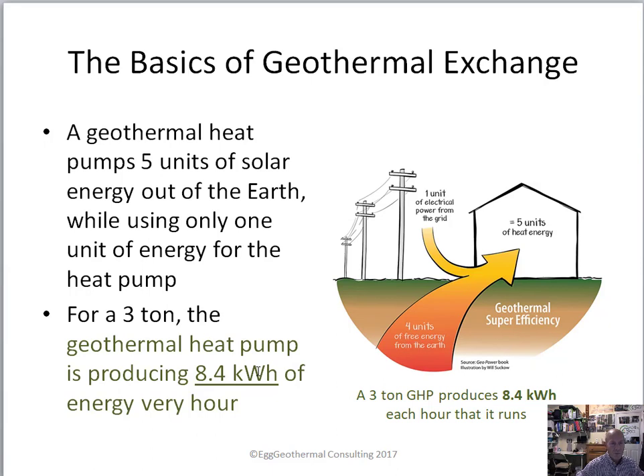In the basics of a geothermal heat pump — and this will apply to air source also — a geothermal heat pump uses one unit of electricity from the grid to pump roughly four units of free energy from the earth. This is depicting a heating mode. When you add those four units of energy to this one unit of electricity, the heat pump is able to deliver a grand total of five units of energy. In this three-ton heat pump example, a three-ton heat pump can produce 8.4 kilowatts of heat every hour it runs.